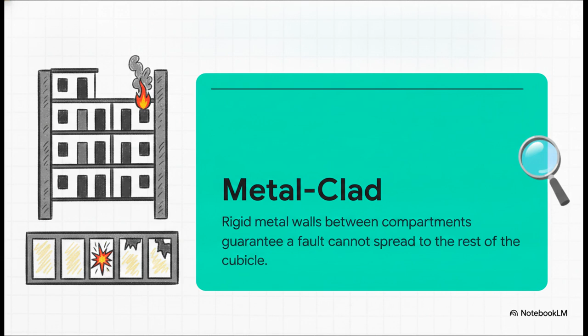Section 3. Inside metal-clad construction. Let's mentally open up that metal door. I want you to imagine an apartment building. If one unit catches fire, thick concrete walls guarantee that the fire absolutely cannot spread to the unit next door, right? That is exactly what metal-clad construction does inside a switchboard. It utilizes rigid steel walls between the internal compartments. One fault equals one compartment. It guarantees that a failure in one zone is totally isolated and cannot destroy the whole board.